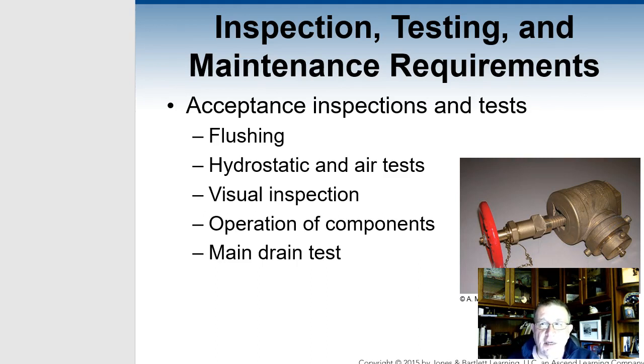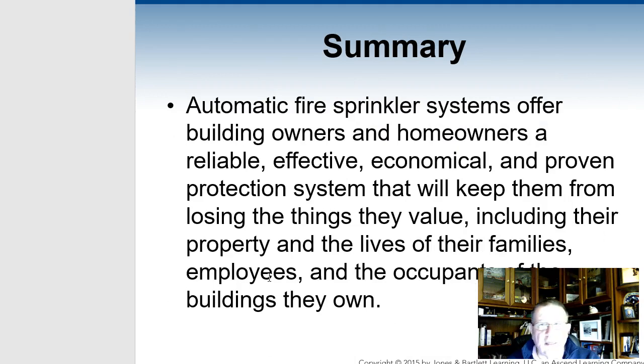And one of the things you have to look at is this particular valve that you see right here is what they use in a standpipe. Do we need to put pressure reducing valves on the standpipe so the firefighters don't get blown away when they hook a hose to it? Most of the time you run into a situation where the standpipe's supposed to maintain 50 to maybe 75 pounds pressure, and it's blowing at 150, 200 pounds, and you hook a 2.5 to that, you're going to be flying through the building.